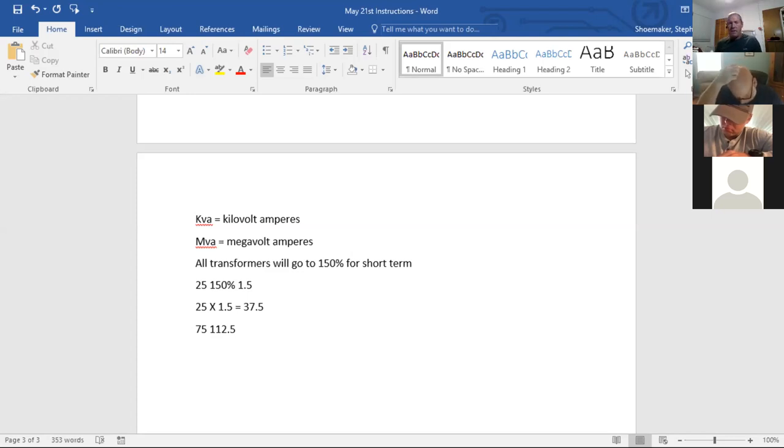So now you know, here on out, you're going to get asked this question. You're going to have it from us, and you're going to have it from the industry. I've got a 75 kVA. What will it go to on an overload? Just multiply by 1.5.